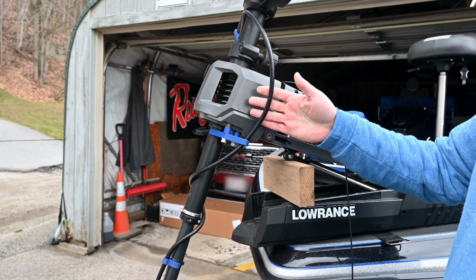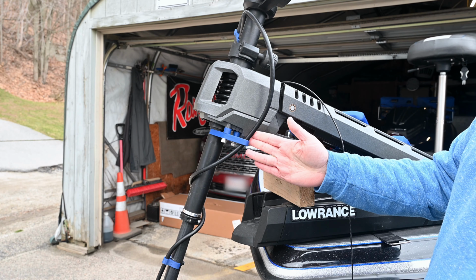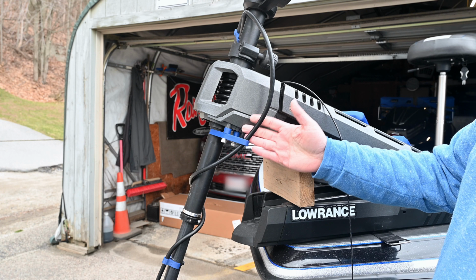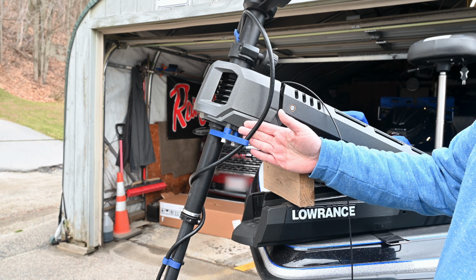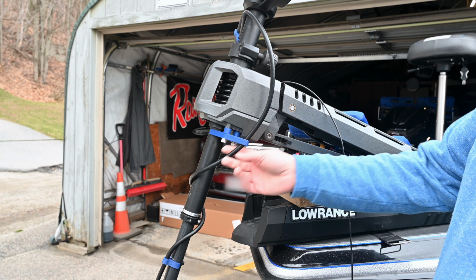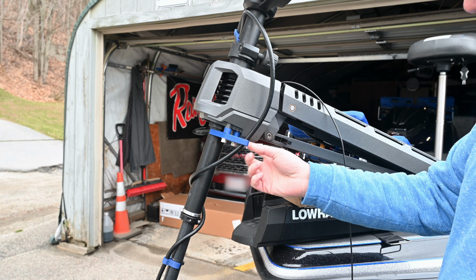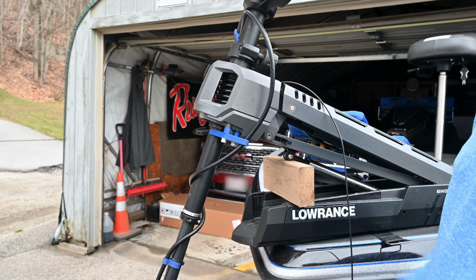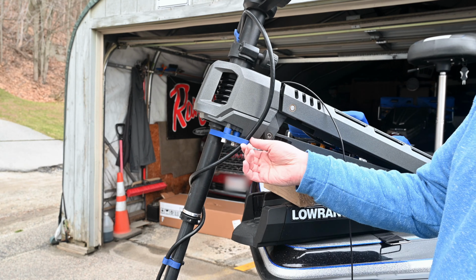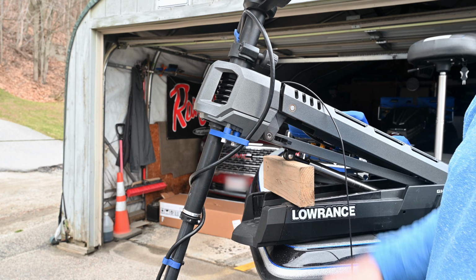This specific active target transducer I took the clamps off to install today, but they've been running these clamps for about a year now, and there's no wear on the cable jacket noticeable from this clamp or from this guide. So even though it is rubbing on the guide, the plastic is a soft enough material that it's not eating through the jacketing of the cable.